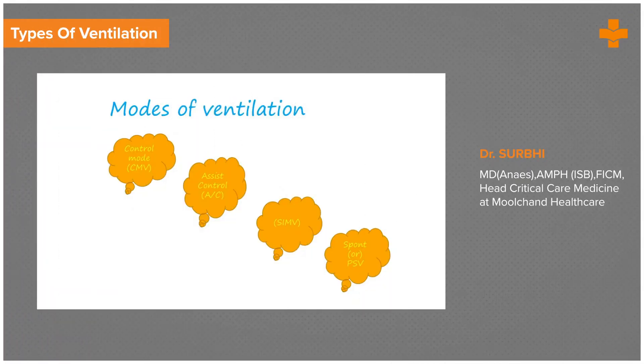Going into the modes of ventilator: the first is Controlled Mandatory Ventilation, which is a totally controlled mode where the patient has no role to play. After that we have Assist Control, where the patient can trigger or start a breath but the rest of the breath is totally controlled by the ventilator. Then SIMV, where the patient breaths are supported only to a certain limit, and Spontaneous, where the patient himself is taking the whole breath and the ventilator has less role to play. So this goes from a totally controlled to a patient-dependent mode.